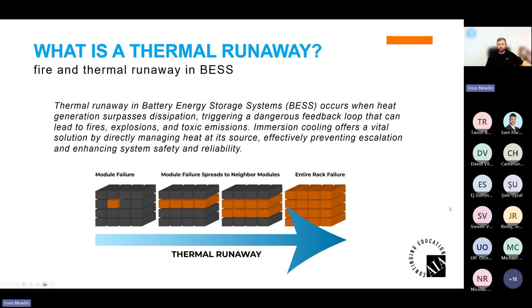So as I mentioned, EPRI did this study with a root cause analysis of incidents since 2012. They broke the categories down into design, manufacturing, integration, assembly, and operation. With lithium-ion batteries, you always have to think there's potential for thermal runaway. So as you're looking at speccing and designing BESS, you have to be aware of the safety risks.